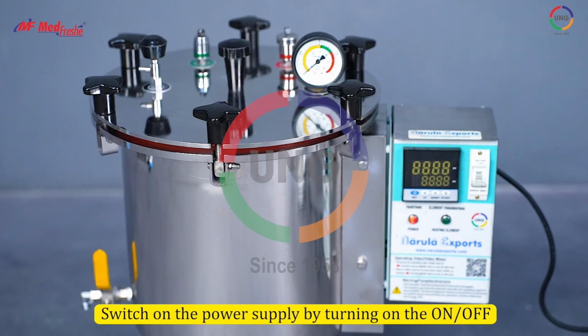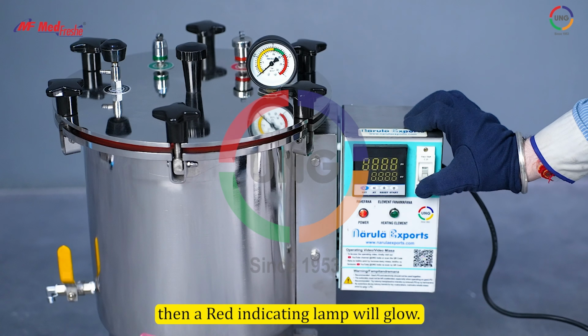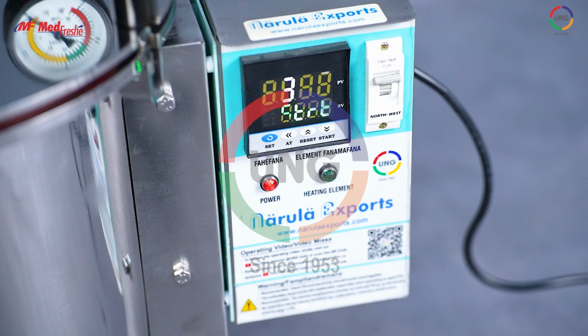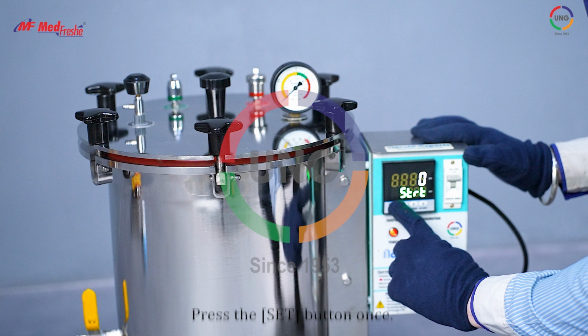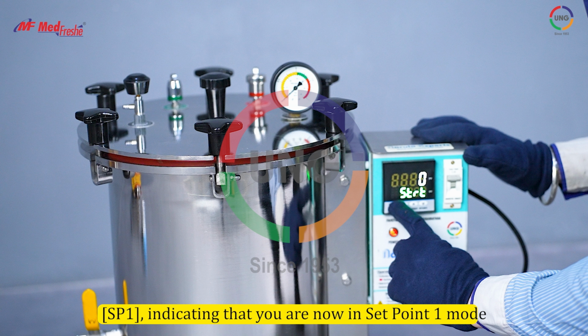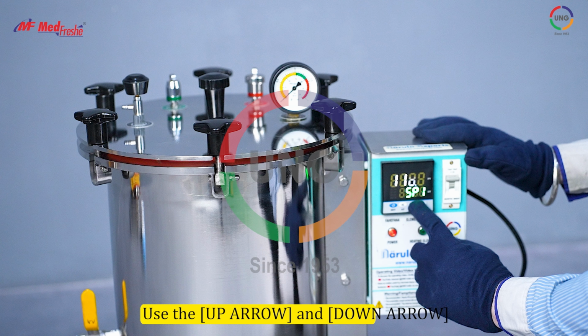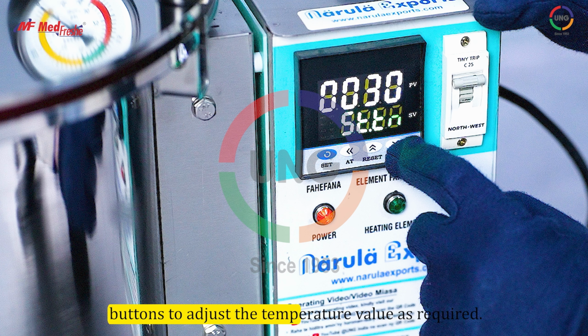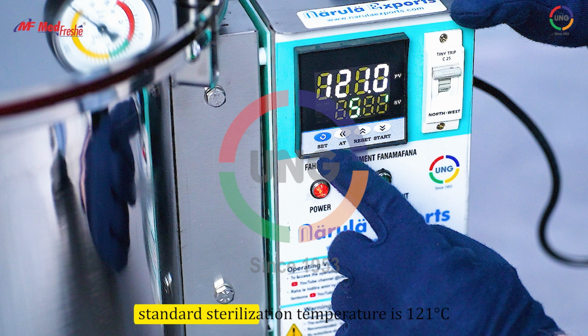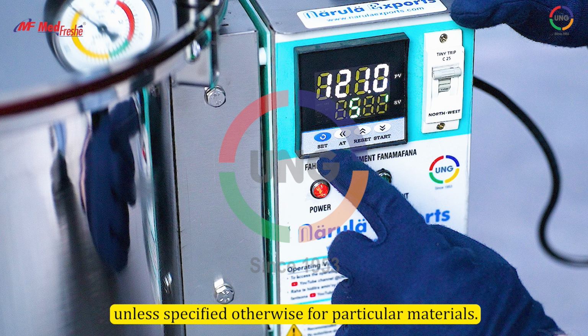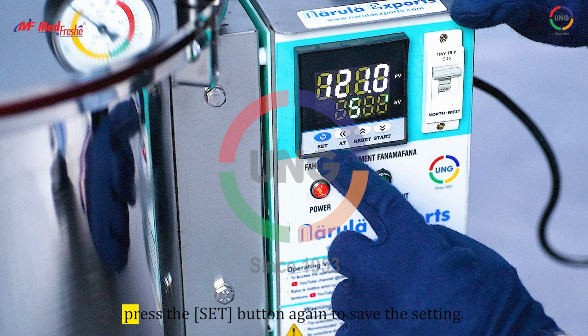Switch on the power supply by turning on the on-off switch, then a red indicating lamp will glow. Set the desired temperature. Press the Set button once. The digital display will show SP1, indicating that you are now in set point 1 mode where the sterilization temperature is defined. Use the up arrow and down arrow buttons to adjust the temperature value as required. The standard sterilization temperature is 121 degrees Celsius unless specified otherwise for particular materials. Once the desired temperature is displayed, press the Set button again to save the setting. The display will confirm that the new temperature has been stored in the controller's memory.